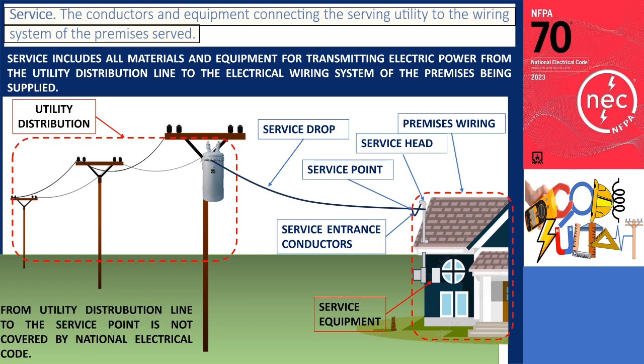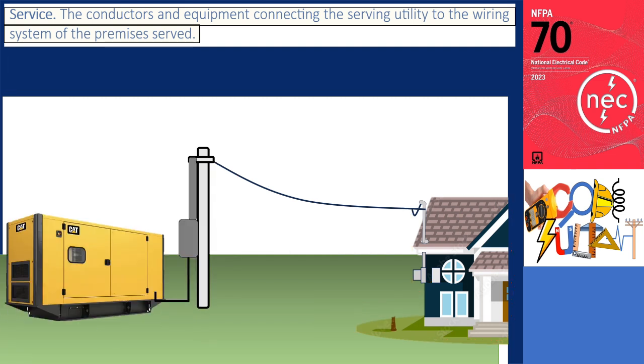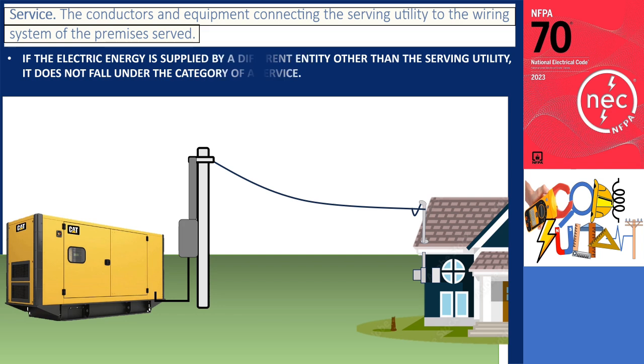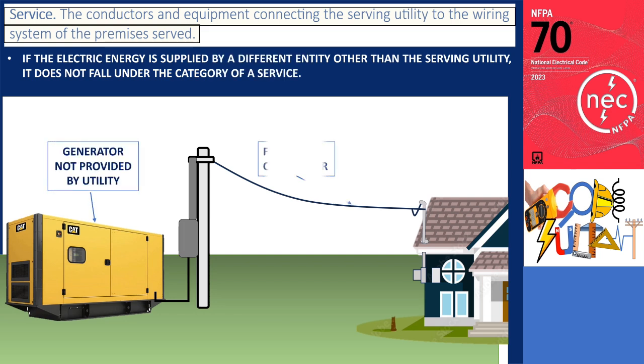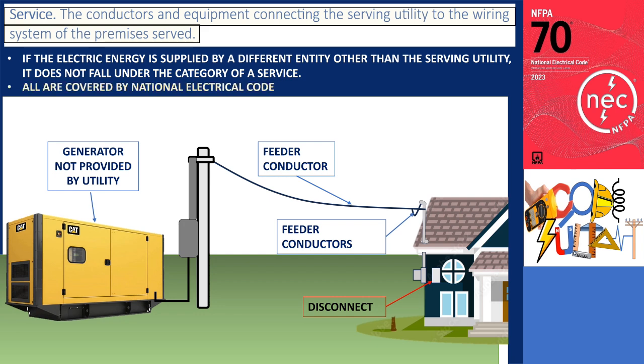However, if the electric energy is supplied by a different entity other than the serving utility, it does not fall under the category of a service. In such cases, the installation would consist of one or more feeders and building disconnects, which are regulated by the NEC.